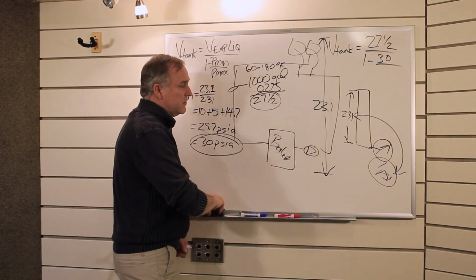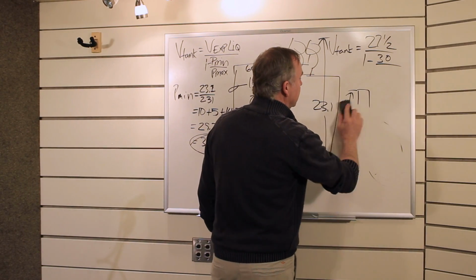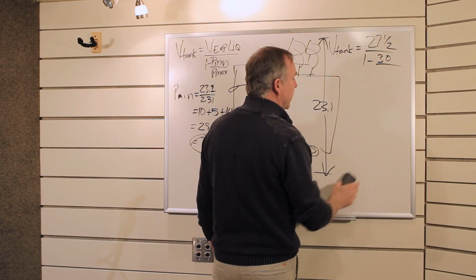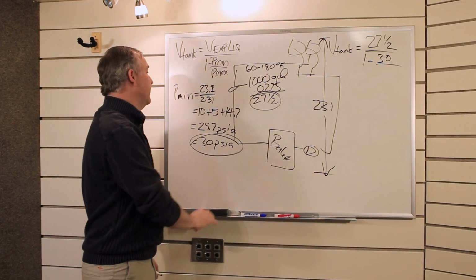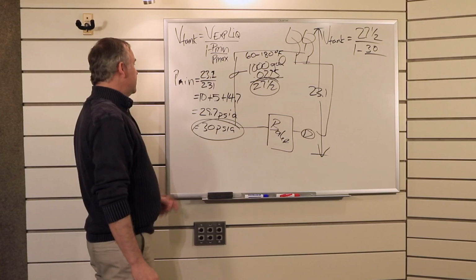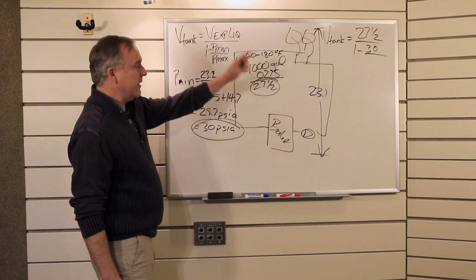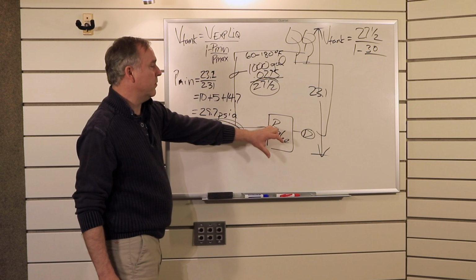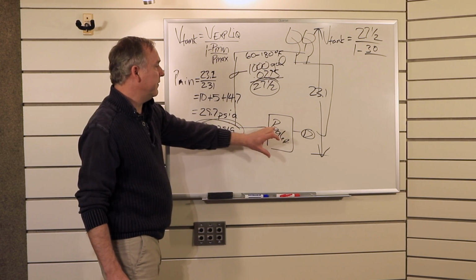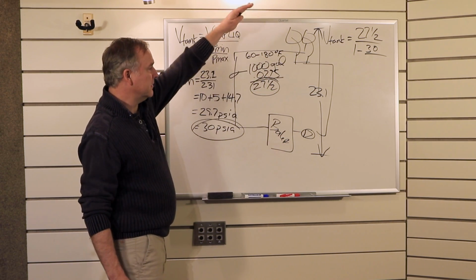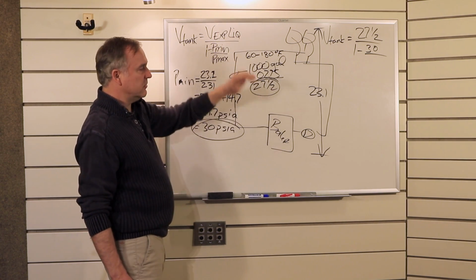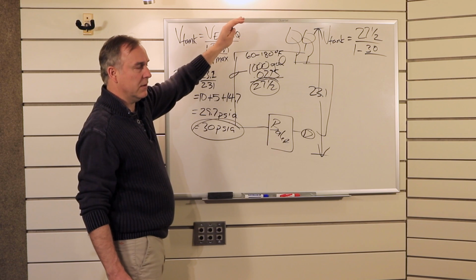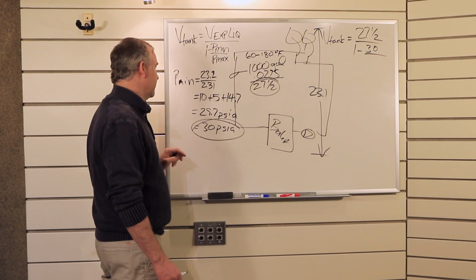Now, if I was doing this in one of the computer selection programs online, there I can plug in gauge pressure and I'll be just fine. Alright, so that's P min, has to do with the height of the system. Again, I'm figuring P min as my equipment and relief valve and fill valve is all down low and the system is above it. If something changes there, if all this stuff is at the top, then the height of the system, going down, doesn't impact things.